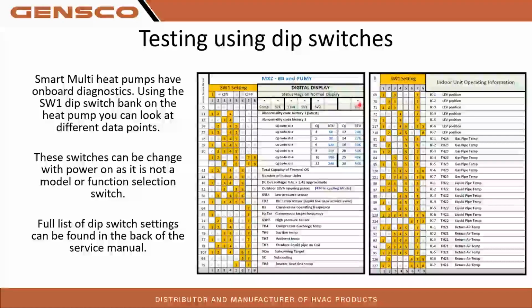And then in your last segment over here, if you have a 1 there, that just means there's high voltage AC being supplied to the unit. So if you're seeing ones, that is what those ones mean. Again, if you see ones, it's not something to panic over. That's a good thing. It means there's no active error code on the heat pump.